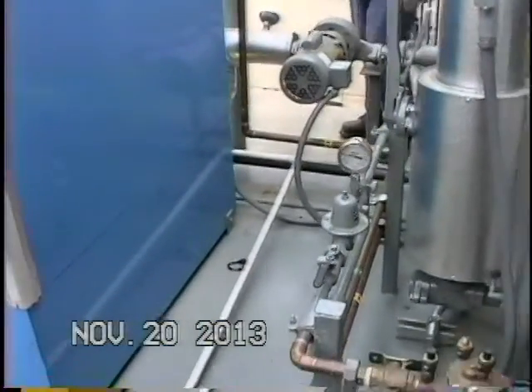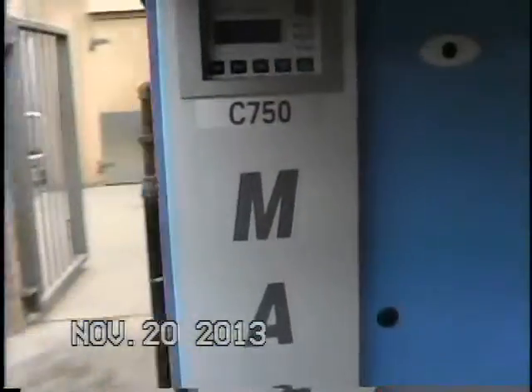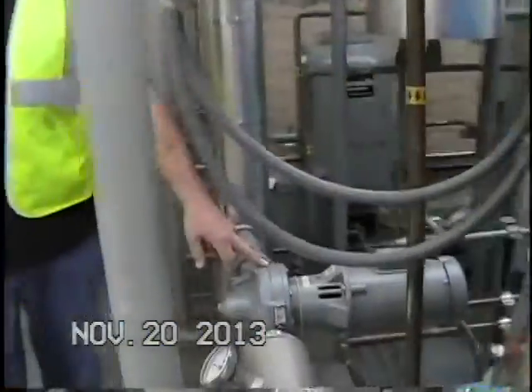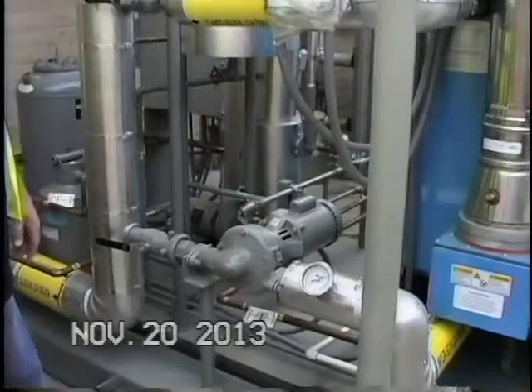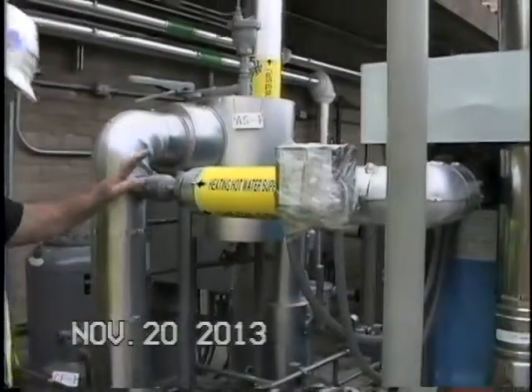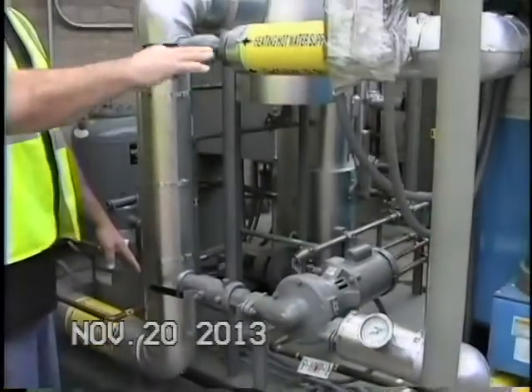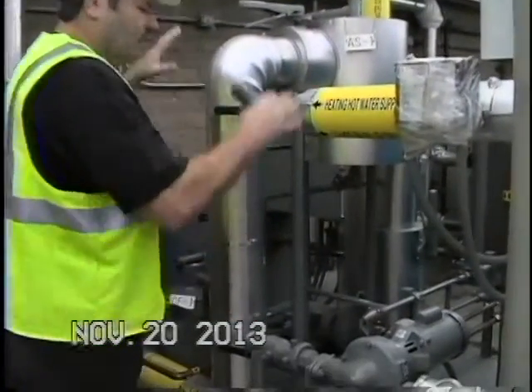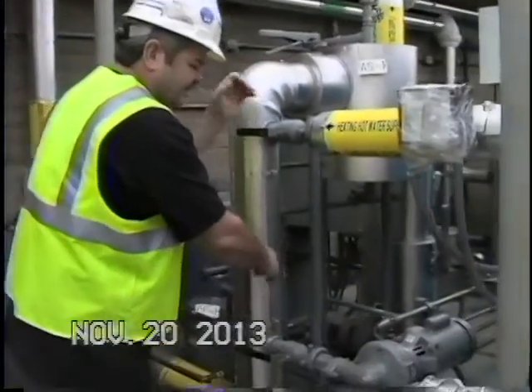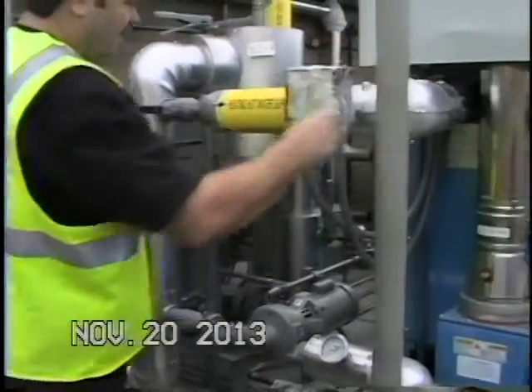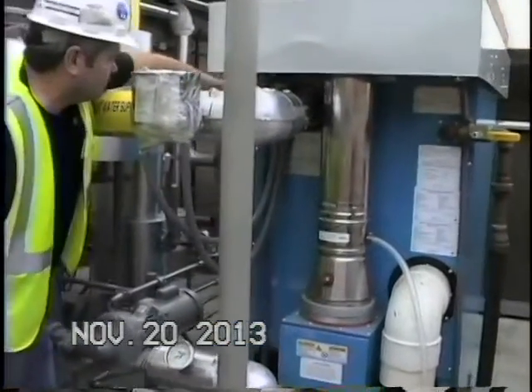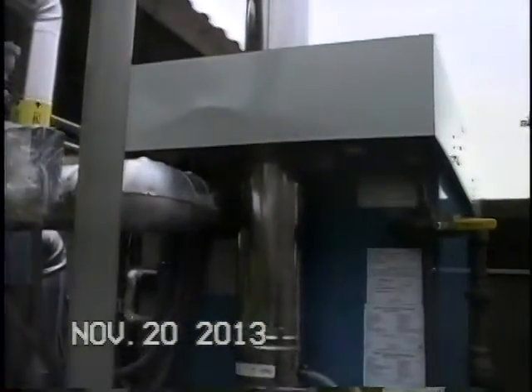Okay, there's your pump, boiler pump, and then you have isolation valves. You have one here and one here. If you need to work on the boiler, piping, whatever, of course your system's going to be locked out, tagged out. You shut these two off, you shut your gas off, and then you can't see it, but there's a pressure relief valve right here. Make sure you get all the pressure out before you open that piping up, okay, because it is under pressure and it is hot. And then I recommend you let it cool before you work on it.